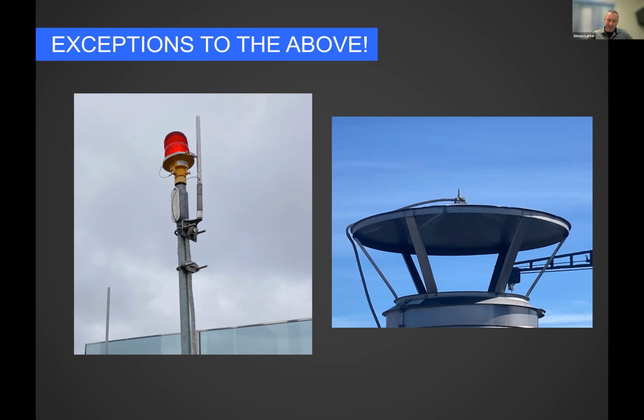So that warning light on the left-hand side there, we're only sticking up 2 inches above it because that's all the clearance the building mechanical equipment operator would give us. The engineer designed it in, and we physically couldn't put the lightning rod up higher than that—they would not let us. So when it comes to who wins in the code, often we lose to the structural engineer or the building mechanical equipment engineer, and we just can't put our lightning rods up much taller. So sometimes when you see an installation like this without the required 10 inches of clearance, that's why—it's because they didn't allow it.